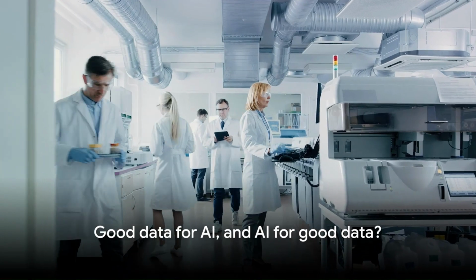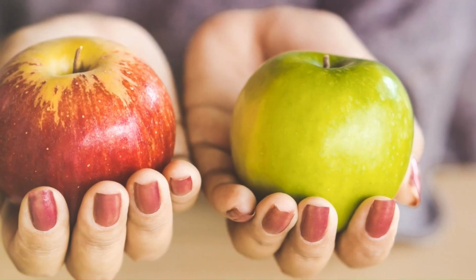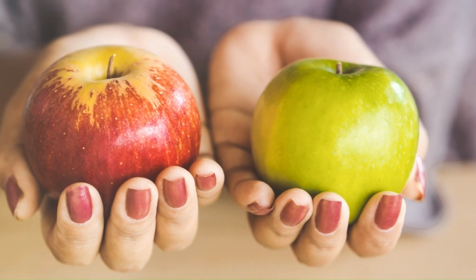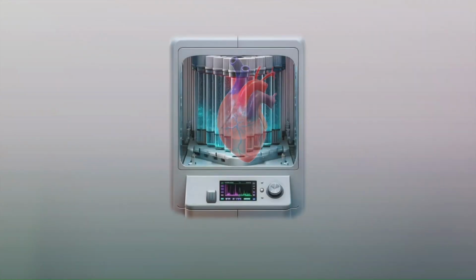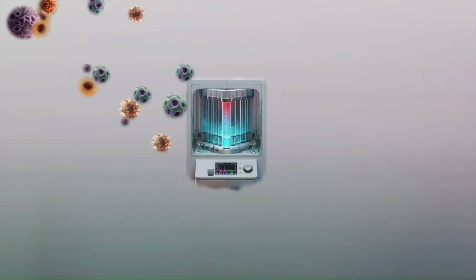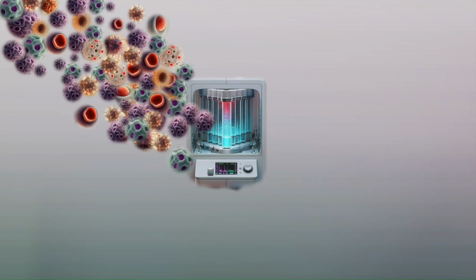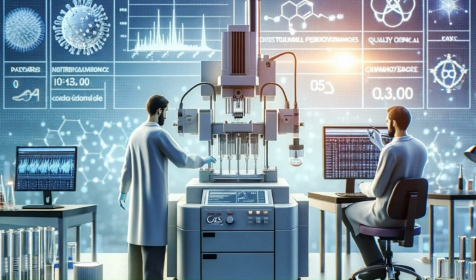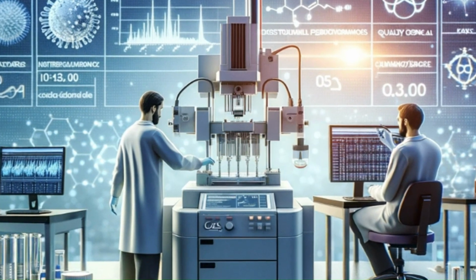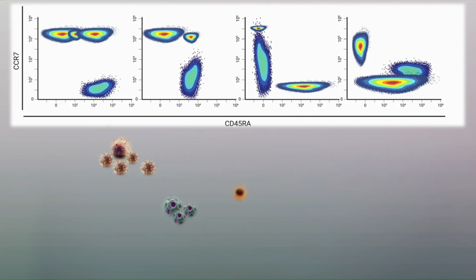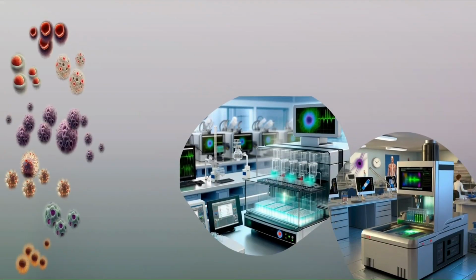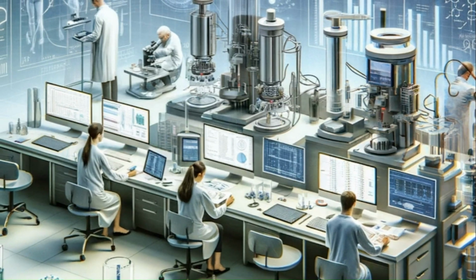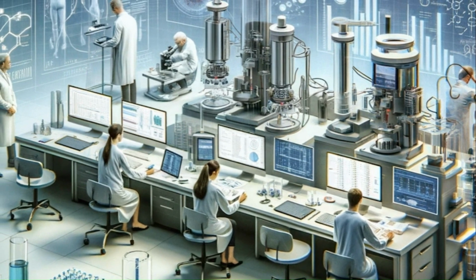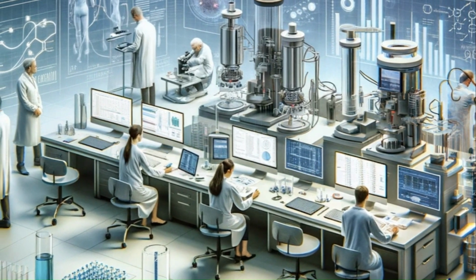Instrument standardization is the process of ensuring that cytometers provide consistent and interpretable data across experiments, both over time and between instruments. Why does this matter? At its heart, a cytometer works by translating invisible biomolecular information into a measurable signal, such as fluorescence. But this process depends on the specific hardware and performance of the instrument being used. Instrument standardization aims at ensuring that variability in cytometry data arises from meaningful biological sources, rather than from the instrument itself.